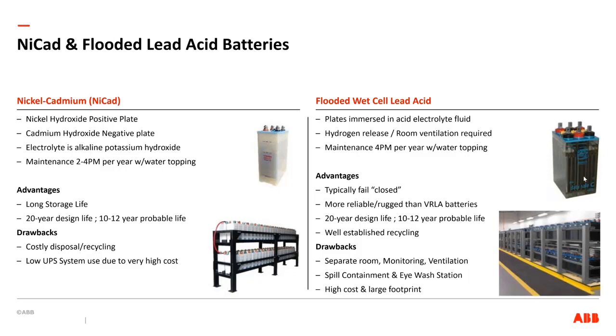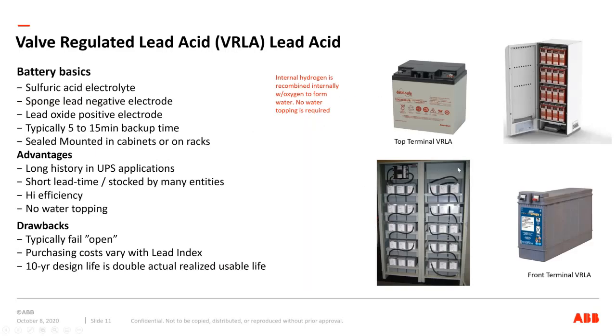And then moving on to the battery that has replaced a lot of the wet cells, the VRLA, which is still a lead acid battery. It's just a lot easier to deal with. There's no topping up of water. And I should say there's a common misunderstanding in the market that some call them sealed batteries. They're not. The V does not stand for sealed. There's a valve there and they can vent. But generally, there's an internal recombination during the discharge and the recharge of the cell. So they're easy to deal with.